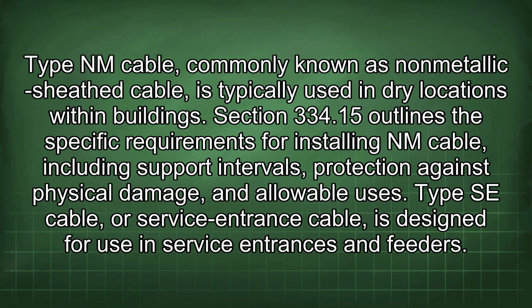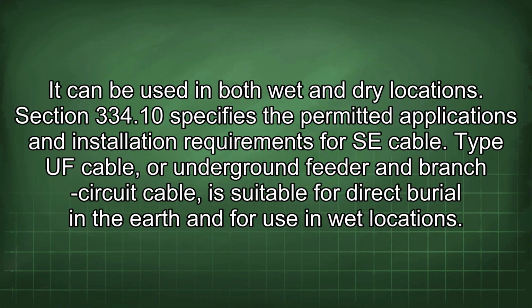Type NM cable, commonly known as non-metallic sheath cable, is typically used in dry locations within buildings. Section 334.15 outlines the specific requirements for installing NM cable, including support intervals, protection against physical damage, and allowable uses. Type SE cable, or service entrance cable, is designed for use in service entrances and feeders. It can be used in both wet and dry locations. Section 334.10 specifies the permitted applications and installation requirements for SE cable.